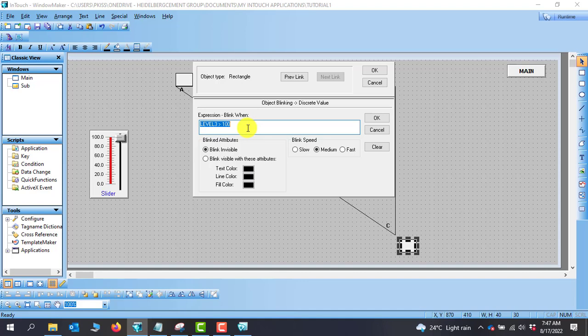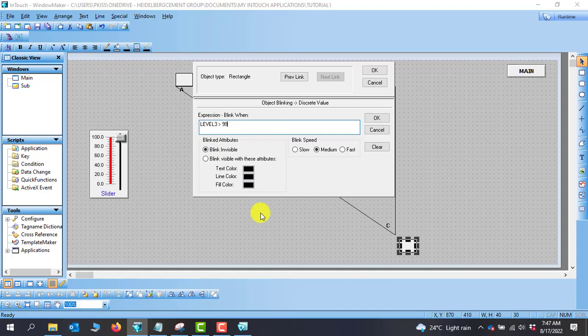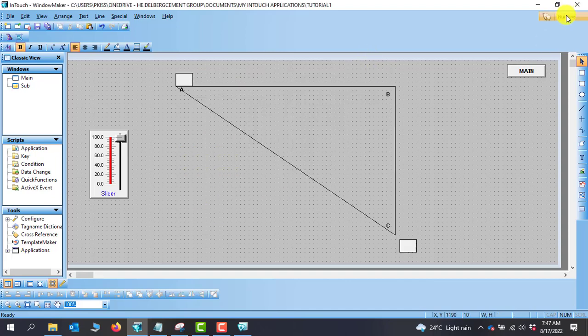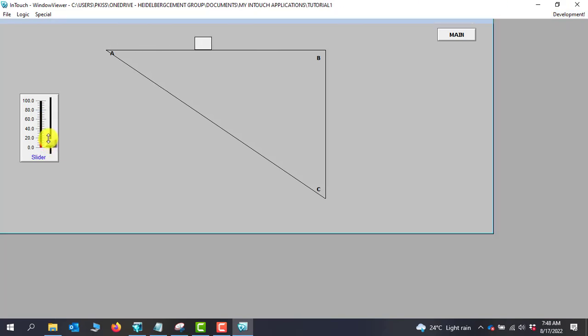We double-click the object and go to Blink under the miscellaneous tab. We need to give an expression: the previous blink used digital points, but this one uses analog, so we give a condition. When the level is greater than 99 it should start blinking, indicating it has reached max. We select the Blink Invisible attribute. Going to runtime, we move the slider through point B, point C, and then immediately at point A the blink appears.